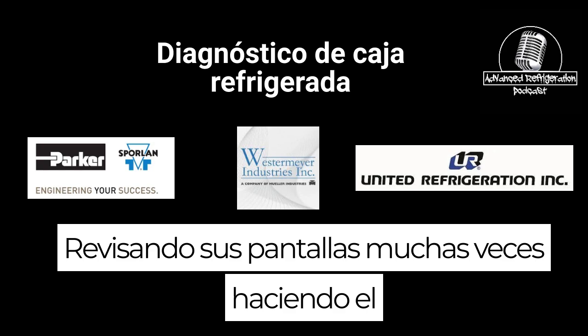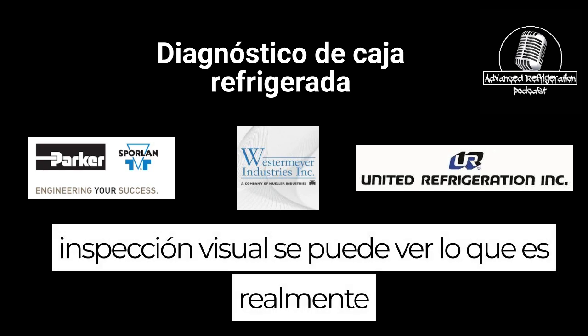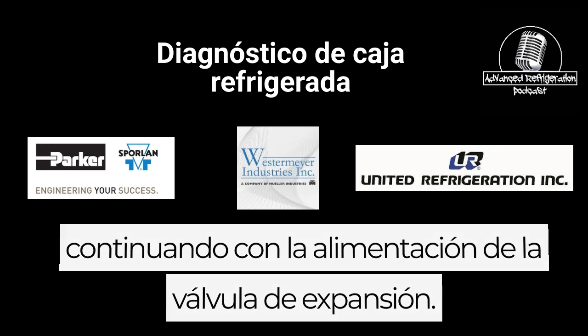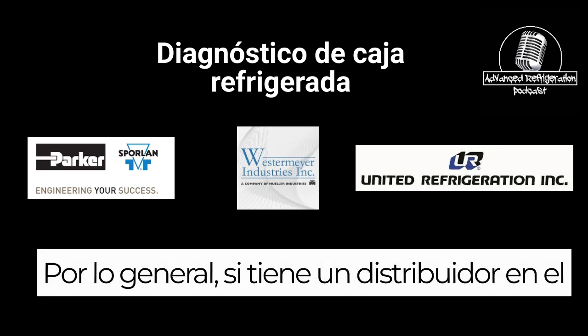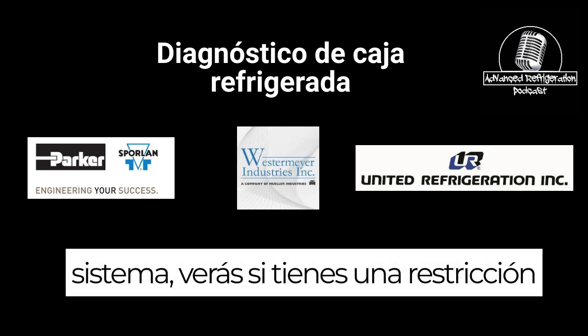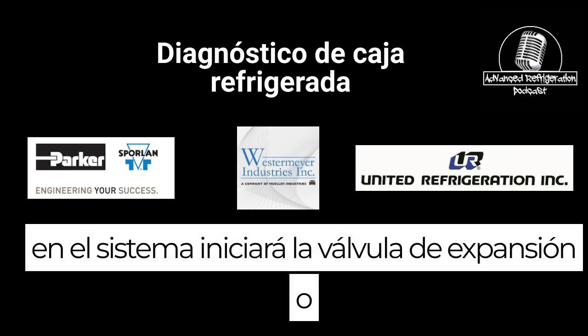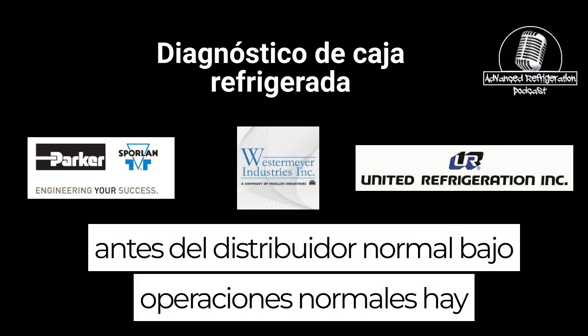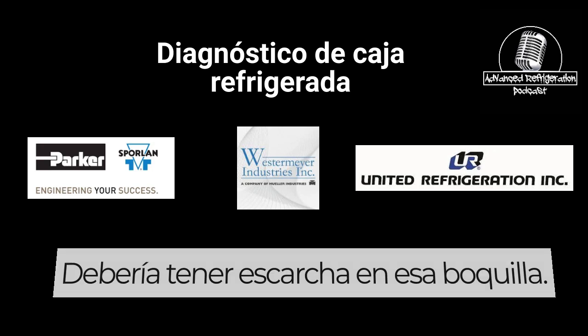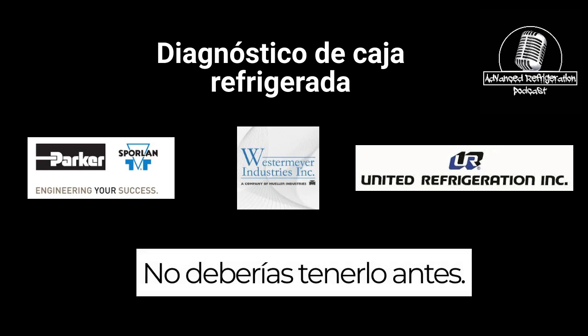A lot of times with doing the visual inspection, you can see what is really going on with the feeding of the expansion valve. Typically, if you have a distributor in the system, and you have a restriction in the system, you'll see frost at the expansion valve or before the distributor. Under normal operations, if there is a nozzle in that distributor, you should be having frost at that nozzle. You shouldn't have it before.